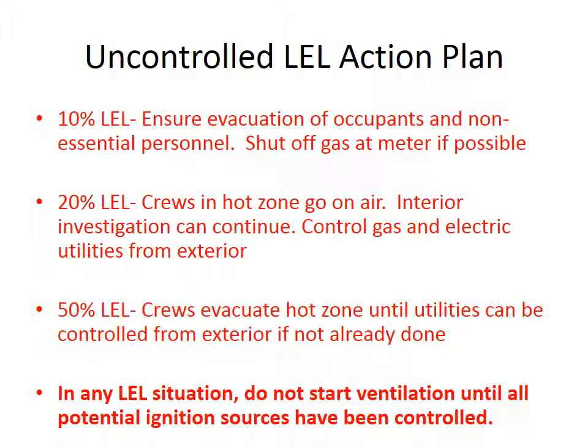At 20% LEL, crews in the hot zone go on air like we talked about before. Interior investigation can continue, with a little bit more importance placed on controlling the gas and the electric utilities from the exterior at this point. At 50% LEL, crews evacuate the hot zone until utilities can be controlled from the exterior, if not already done. So at 50%, we don't know what the source is or we can't control the source. It's 50% and increasing, we're going to pull out.